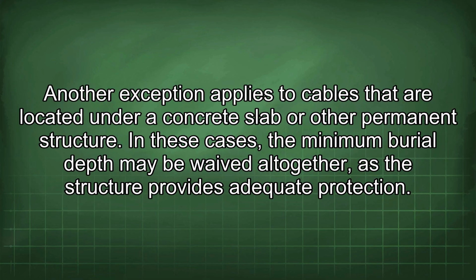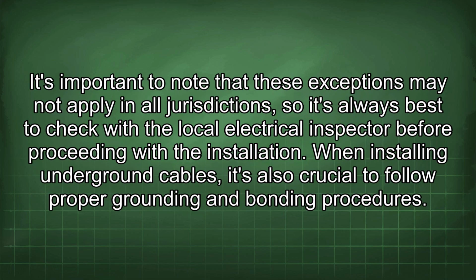Another exception applies to cables that are located under a concrete slab or other permanent structure. In these cases, the minimum burial depth may be waived altogether, as the structure provides adequate protection. It's important to note that these exceptions may not apply in all jurisdictions, so it's always best to check with the local electrical inspector before proceeding with the installation.